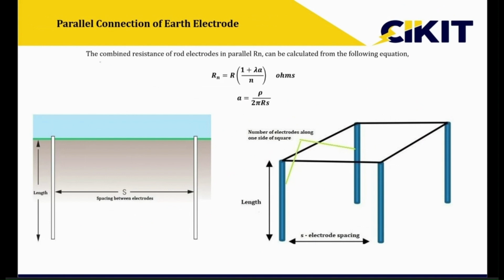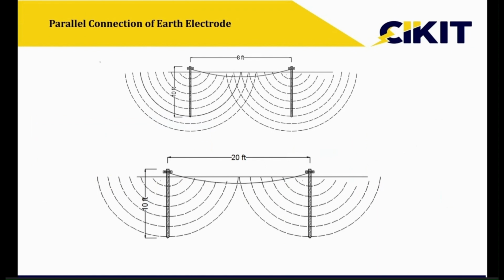The standard has provided the formula for calculating combined resistance also. So when we are working with earthing, we have to use one of the formulas provided by the standard. And one more thing: when we go for parallel connection, the spacing between the electrodes plays an important role. We need to ensure a spacing of at least the length of the electrode. If I'm using a 3-meter electrode, then the spacing should be a minimum of 3 meters. So that should be ensured. If I have very low spacing, then the resistance value will be higher. That is the reason we said it depends upon the surrounding environment. If I install two electrodes at 1 meter spacing, 3 meter spacing, and 6 meter spacing, obviously the resistance value will be different for different configurations, because it depends upon the spacing between the earth electrodes also.